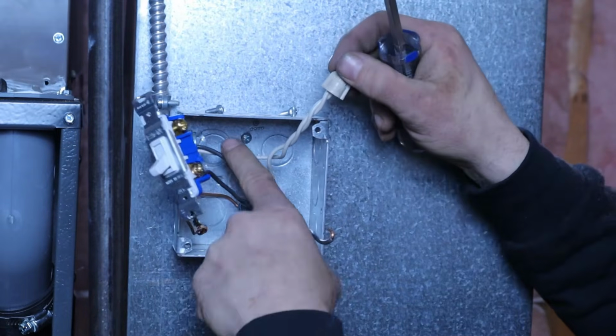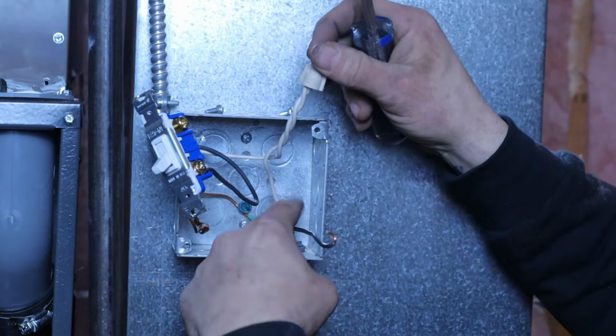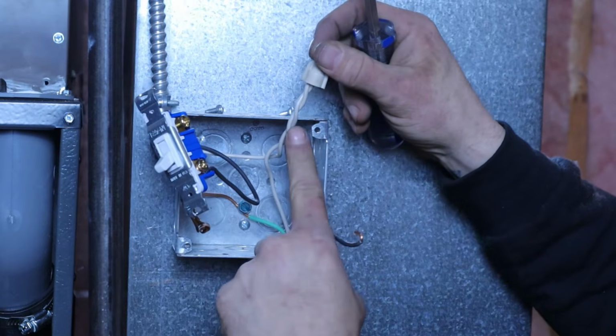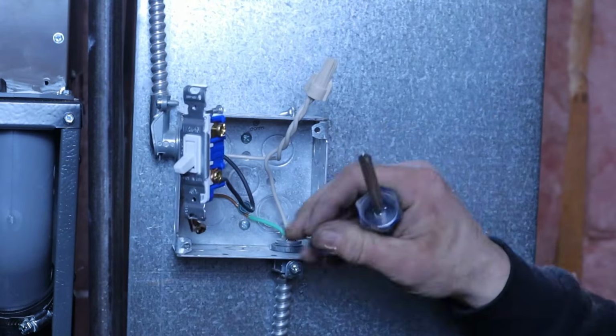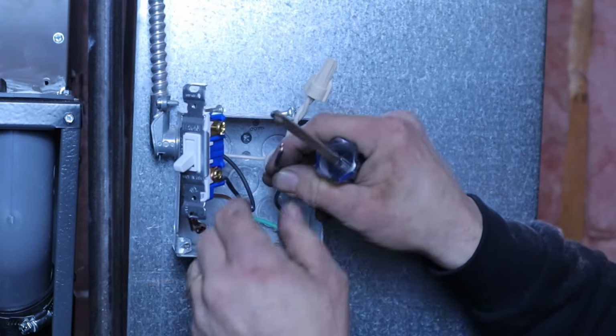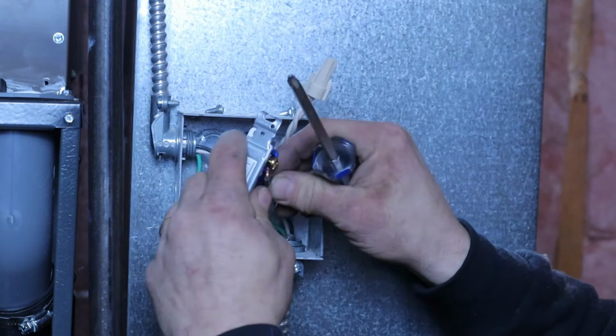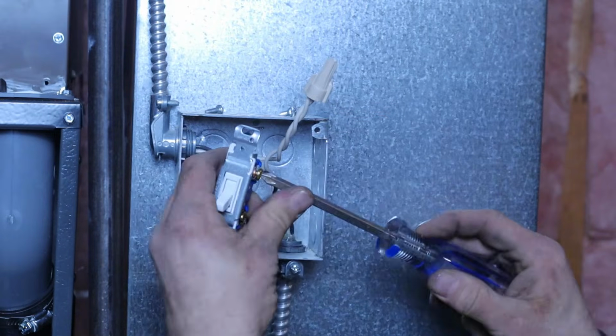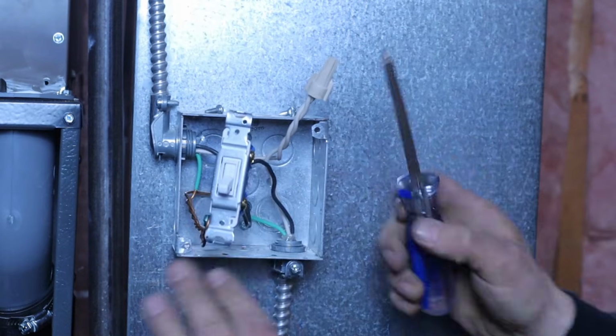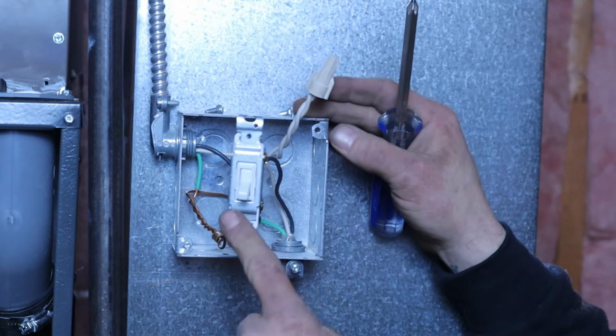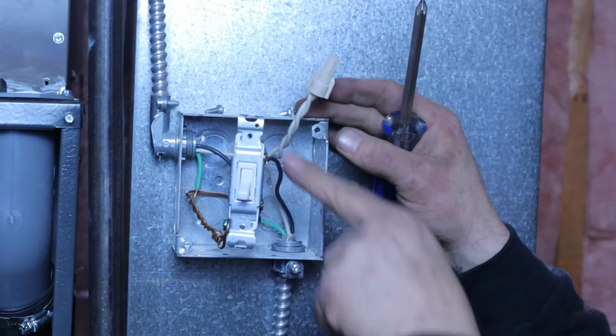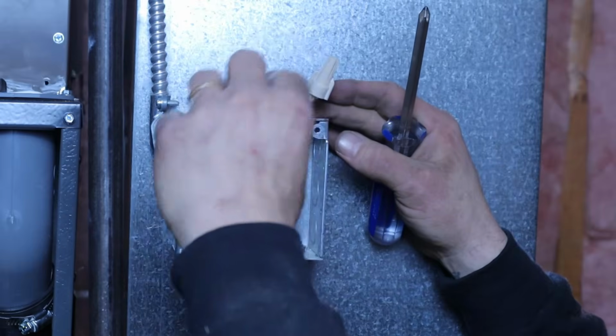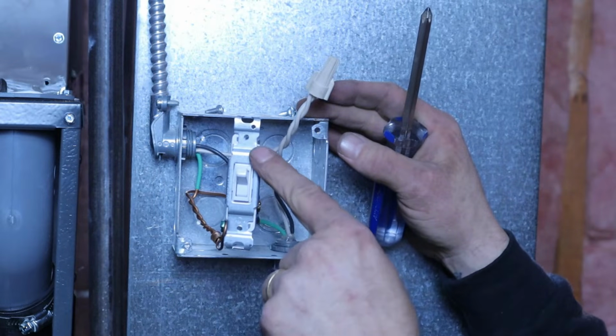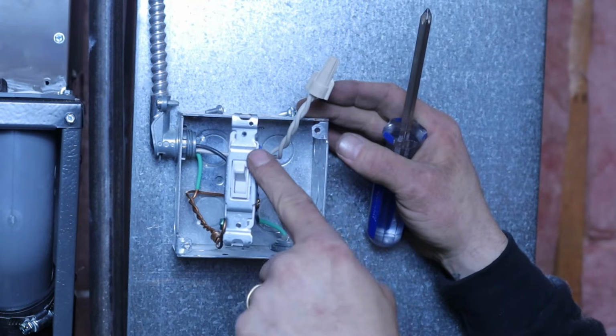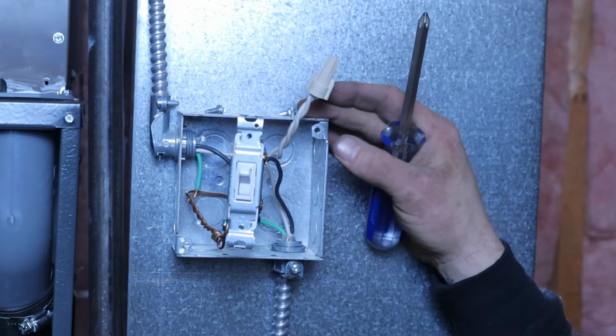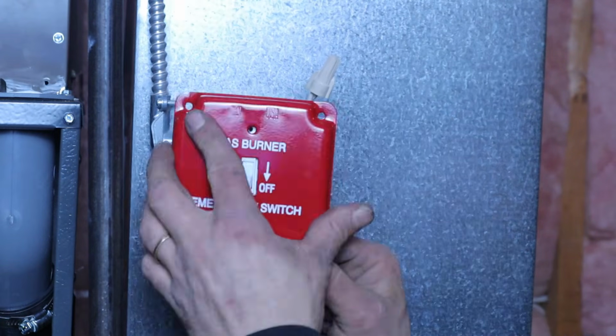Okay, we have our neutral wire. It's already tied in and going down to our outlet. So I'm going to take the black wire that's also going down to our outlet and eventually to the furnace, and tie that in up top. So basically the way I have it configured here, when it's off, it's pointing towards the power coming in, and when I turn it on, up, it's going to send the power to our load, which is our furnace, and the power is going to travel down to the outlet.